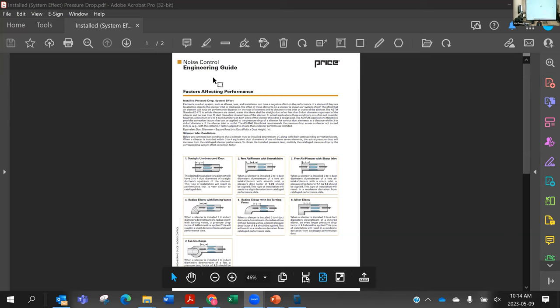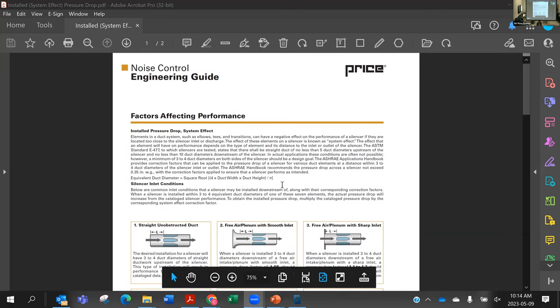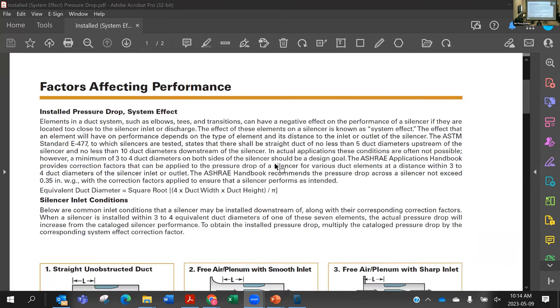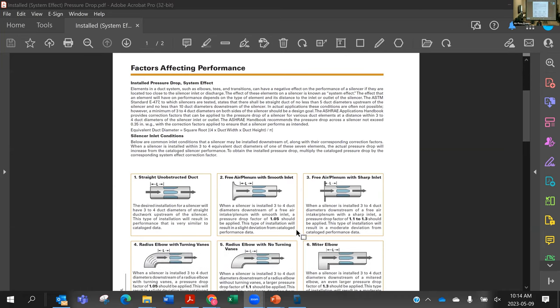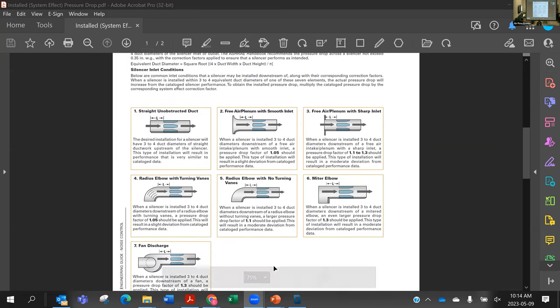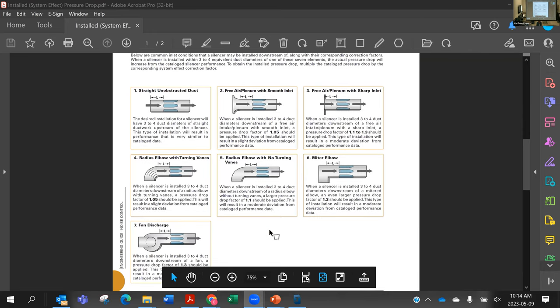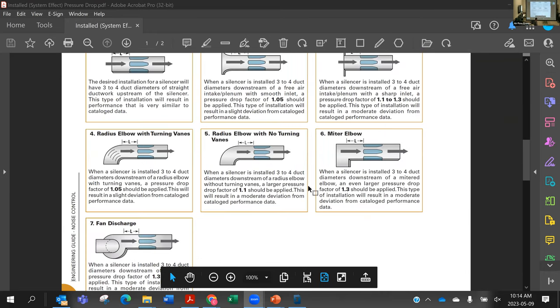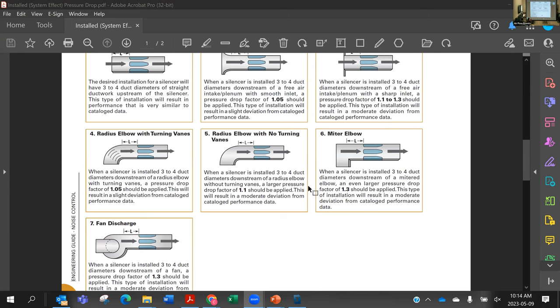share screen. We actually have a really good engineering guide. You can find it on our website. What it references is basically whenever you have a silencer installed near some sort of duct element, you want to try and keep that 3 to 4 equivalent duct diameters either upstream or downstream from it, or you need to apply an equivalent system effect.